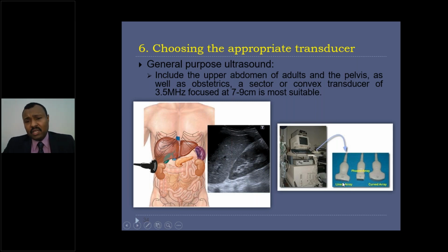And in this image, you can see the three forms of ultrasound transducer. We mentioned linear array, we mentioned curved array, but this kind of probe is known as a phased array transducer. And as we are going to see shortly, it's a specialized kind of transducer. It can scan the areas that are obscured by the ribs, because it has the ability to send an ultrasound beam between the ribs, especially in the intercostal spaces. And it's a great value probe that is going to be used especially in echocardiographic examination, as I will show you shortly.